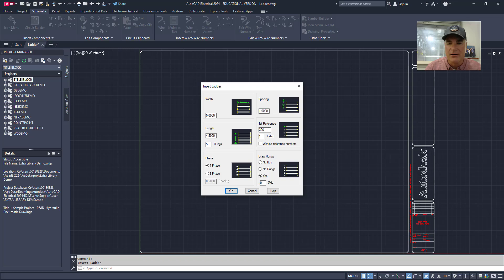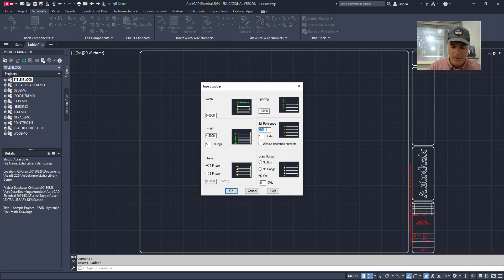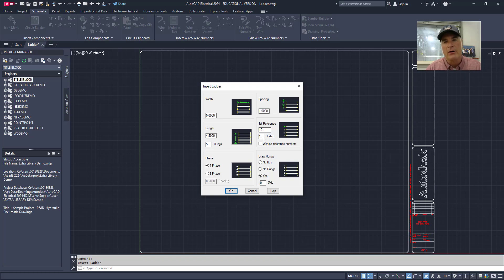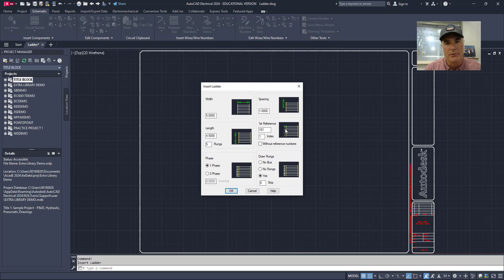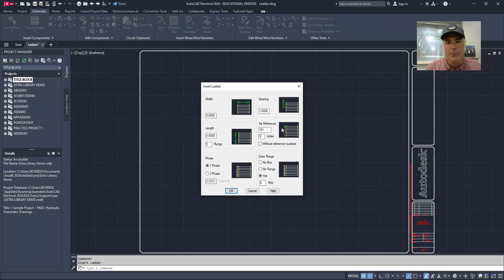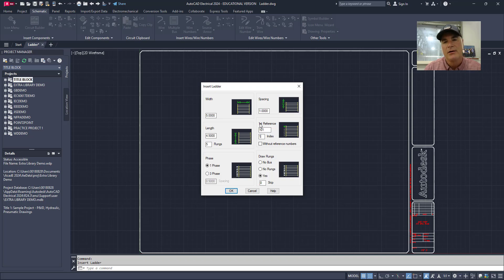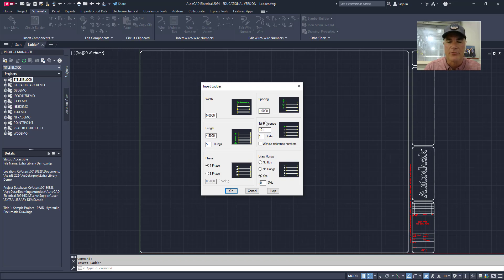Then I can give it the first reference number. The ladder will have reference numbers going down the left hand side beginning with this number. So I'm going to say 101. And then I can tell it how I want to index each rung afterwards. If I have this set as one, the next rung will be 102, then 103, then 104. If I have this index set at two, it will skip every even number: 101, 103, 105. And if I change this to three, it will skip two in between: 101, skip 102 and 103, then 104, skip 105 and 106, then 107.